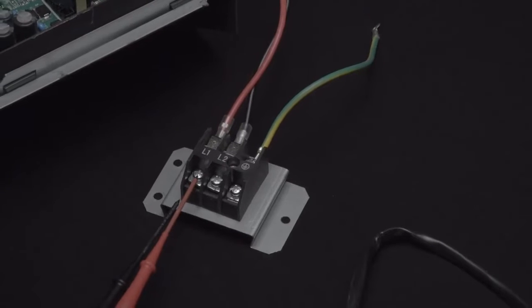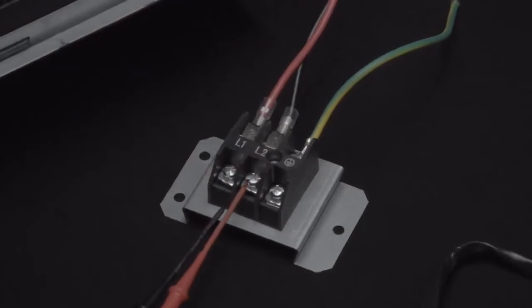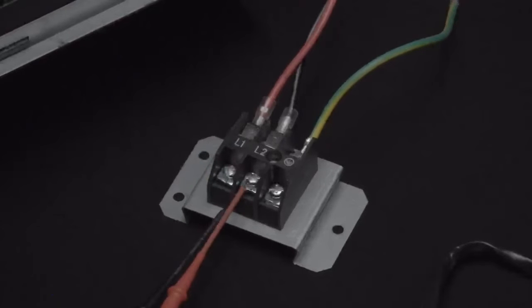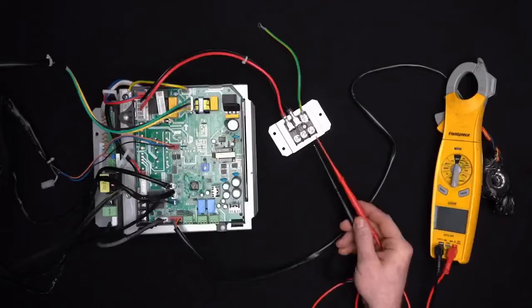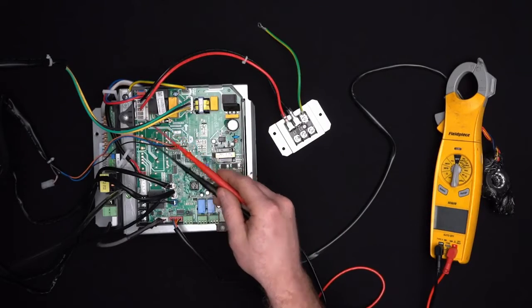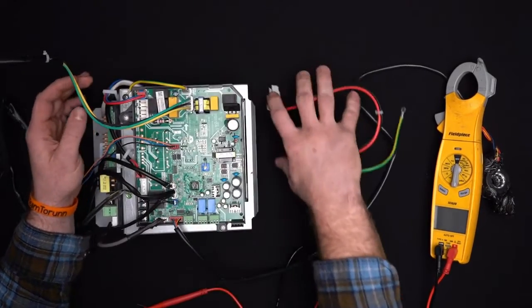If you measure this L1 to ground, you should get between, depending on if you have 208 or 240, you should get your line 1 voltage, and then between L2 and ground, you should get your line voltage between L2 and ground. That goes to the board to our connector here with the red and black. We're going to go ahead and remove this and get this out of the way.